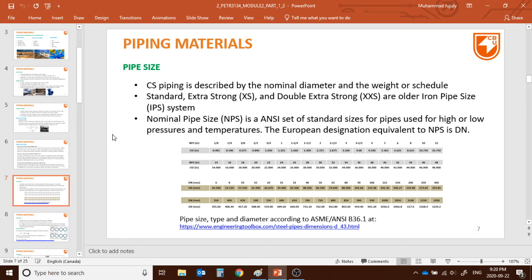The older system called IPS (Iron Pipe Size) had different sizing like Standard, Extra Strong (XS), and Double Extra Strong (XXS). Those terms can be confusing but it's still worth knowing. Now we mostly use NPS — Nominal Pipe Size — a standard used for pipelines at high or low pressure and temperature. The European equivalent is DN (Diamètre Nominal), sized in millimeters.